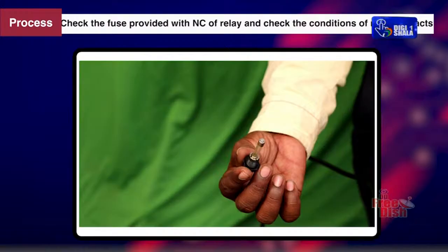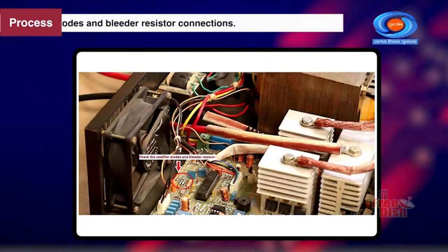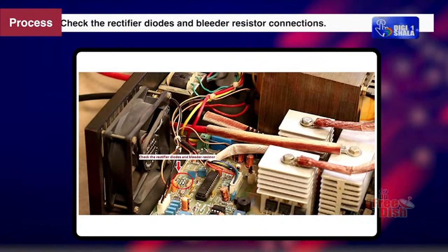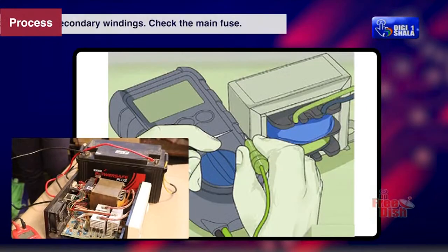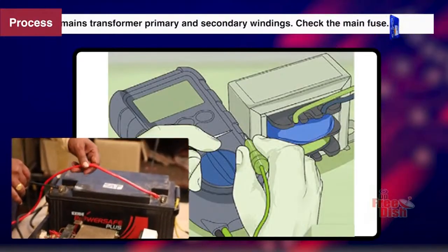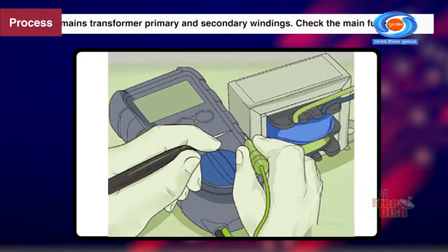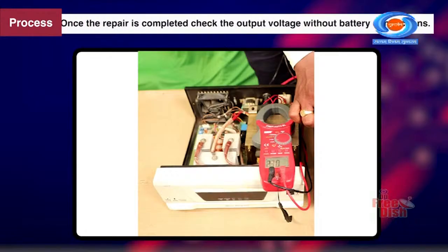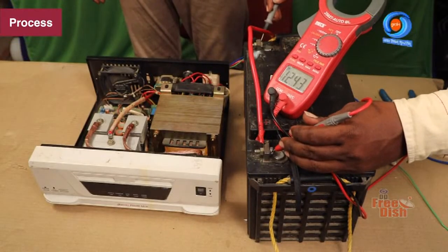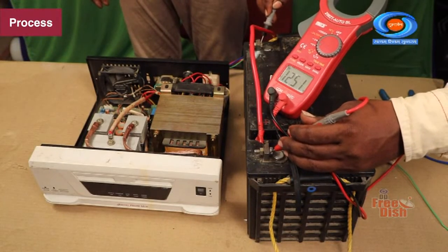Check the fuse provided with NC of relay and check the conditions of relay contacts. Check the rectifier diodes and bleeder resistor connections. Check the mains transformer primary and secondary windings. Check the main fuse. Once the repair is completed, check the output voltage without battery connections. Connect the charged battery if output is available and operate it and ensure it's working.